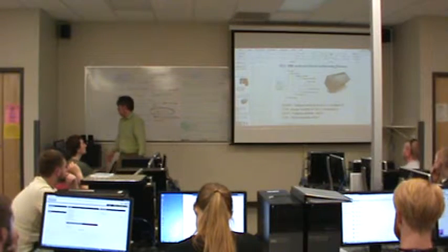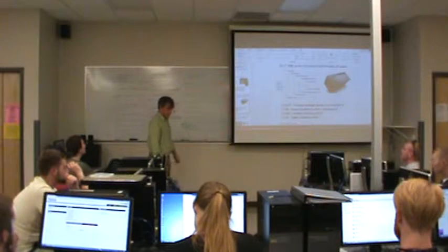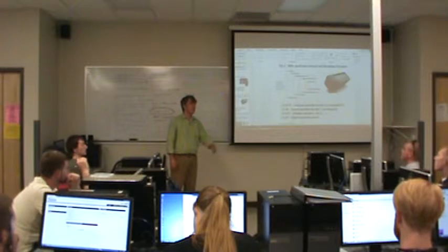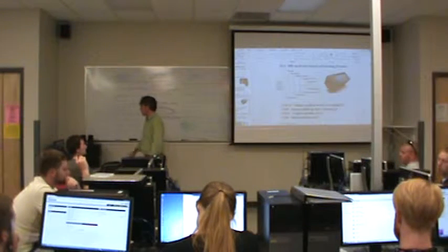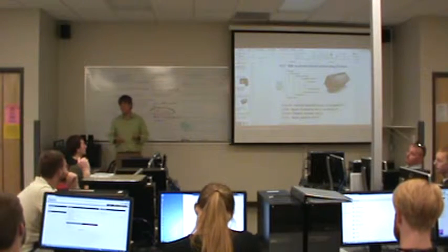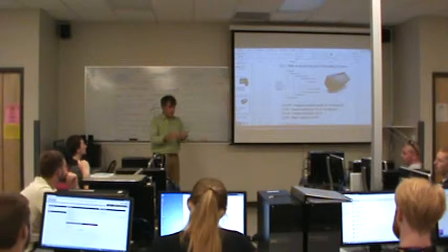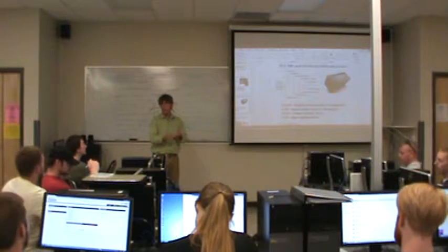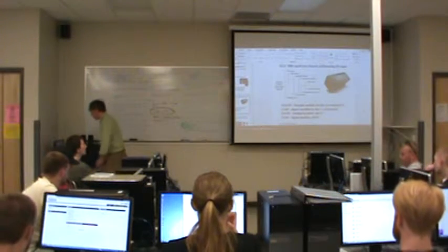And if you go to another manufacturer, like I did for my own system, I bought a lot of AutomationDirect. Click Koyo, though, is the name of it. If you buy that, then you have to learn the syntax for how you address inputs and outputs. The general idea is that you need to know whether you're talking about an input or an output or something else, and for addressing, you need to know what word and what bit. Those are the big three things you need to know in order to get a PLC to talk to its inputs and outputs.